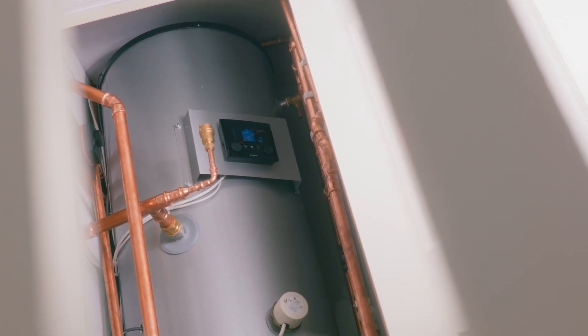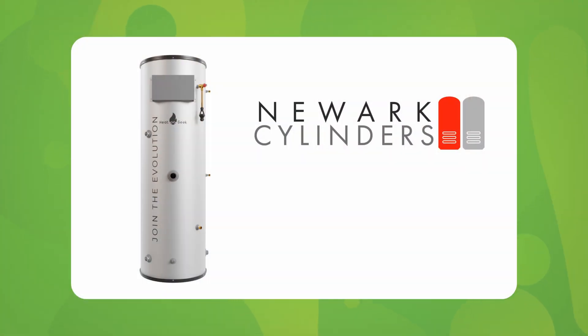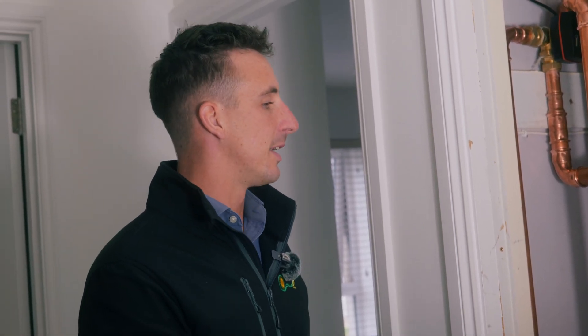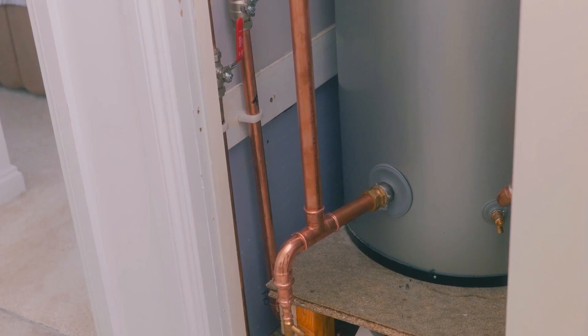As part of your heat pump install it's likely you'll have to change your hot water tank to one with a larger coil. Most tanks are designed for boilers, whereas this tank is designed predominantly for a heat pump — it has a very large coil of six square meters, which is very large for a water tank. It's designed by Newark with HeatGeek, who offer training courses for installers to upskill to low carbon technologies. This is the 300-litre version. The space was very tight but we're aiming for a really efficient system — this coil runs on 35mm and everything is slightly oversized to ensure correct flow rate and heat transfer.